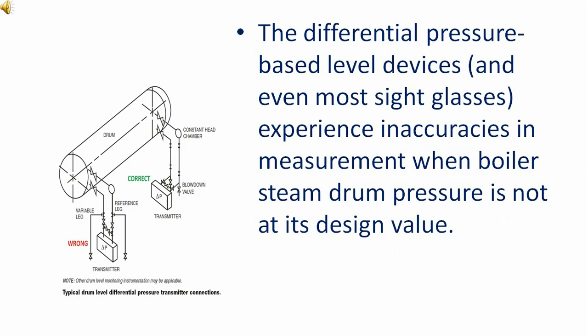The differential pressure based level devices and even most sight glasses experience inaccuracies in measurement when boiler steam drum pressure is not at its design value.